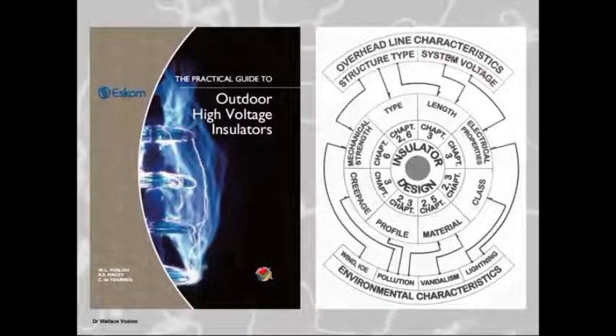So depending on the system voltage, the actual length of the insulator is selected, and depending on the structure type, the length of the insulator is selected. So the structure type and the system voltage determine the length of the insulator, and you can read about it in chapter 3. You see now how to use this chart. So let's take a look. We go through this chart and have a quiz.